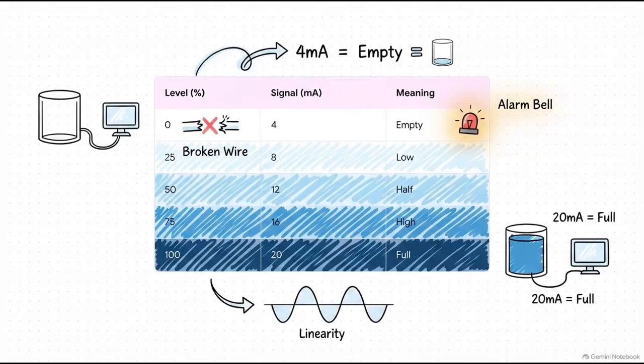And there is a really elegant piece of math behind this communication that acts as a genius built-in safety feature. You might be wondering, if the tank is at 0%, why isn't the signal 0 milliamps? Why start at 4? Well, if the signal was 0 for an empty tank, the computer wouldn't know the difference between an empty tank and a wire that just physically snapped. By making empty equal to 4 milliamps, if a wire ever breaks and the signal drops to absolute 0, the system instantly knows there's a critical fault and sounds an alarm. From there, it scales up perfectly to 20 milliamps for a 100% full tank.